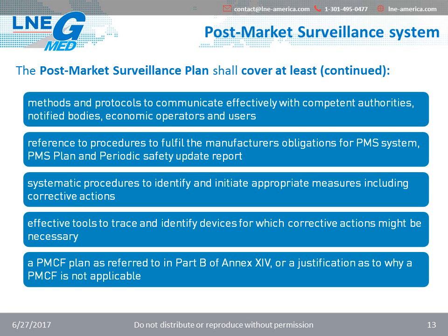but also methods and protocols to communicate effectively with competent authorities, notified bodies, economic operators, and users. Reference to procedures to fulfill the manufacturer's obligation for post-market surveillance system, post-market surveillance plan, and periodic safety update reports.